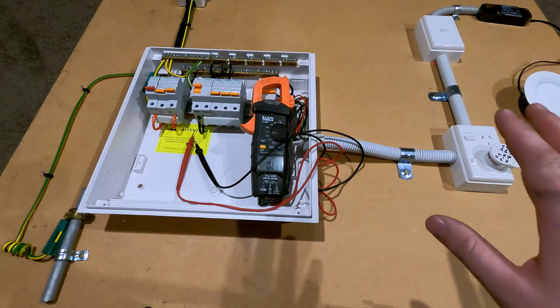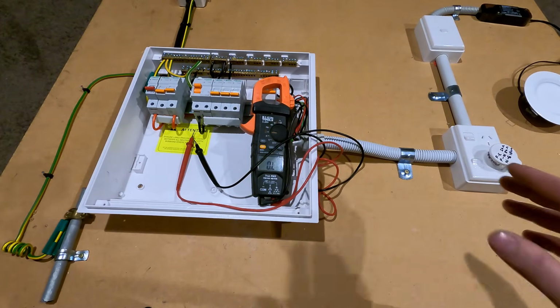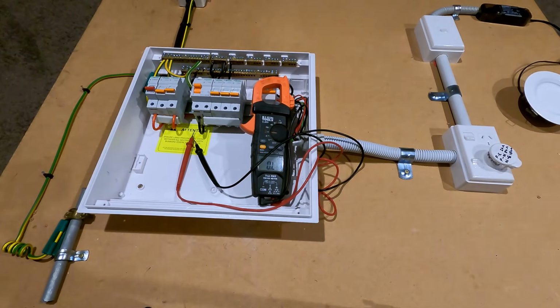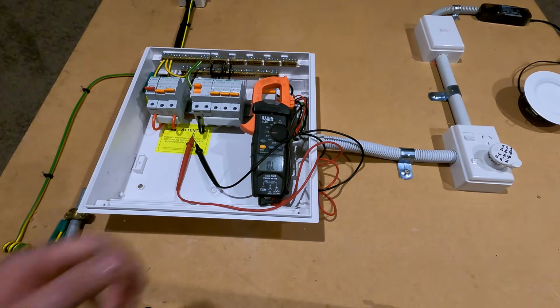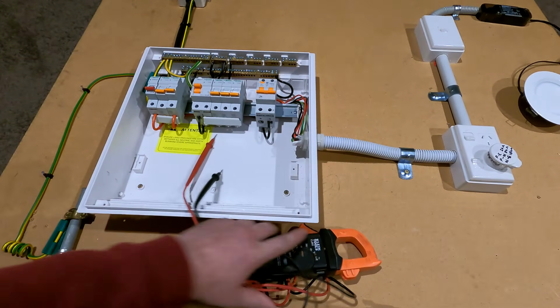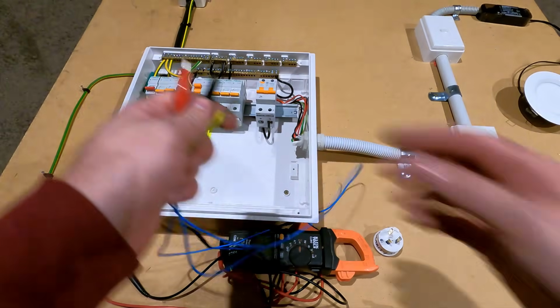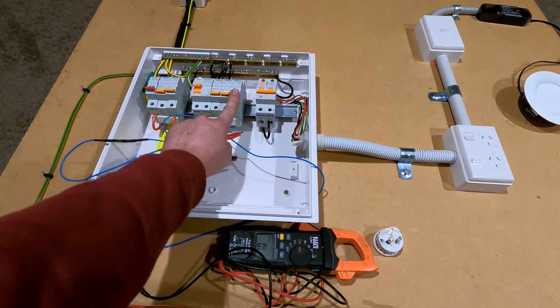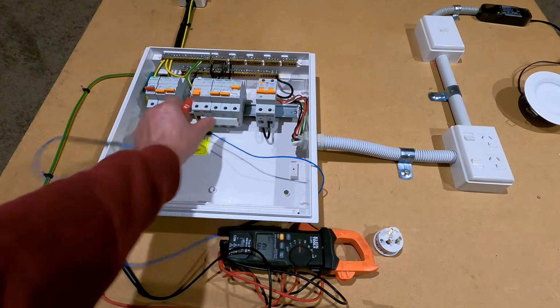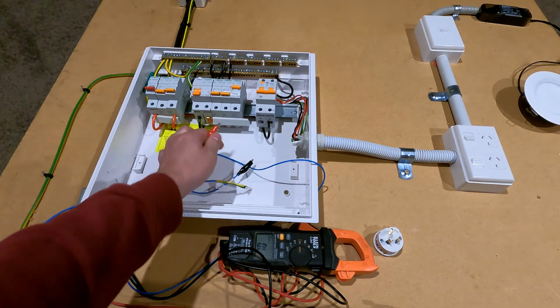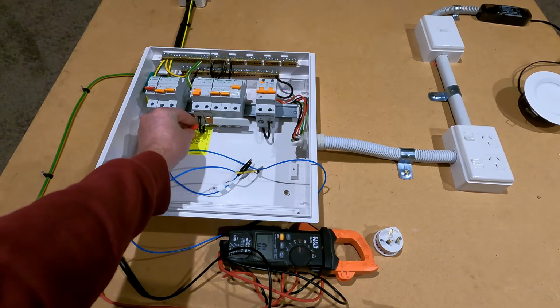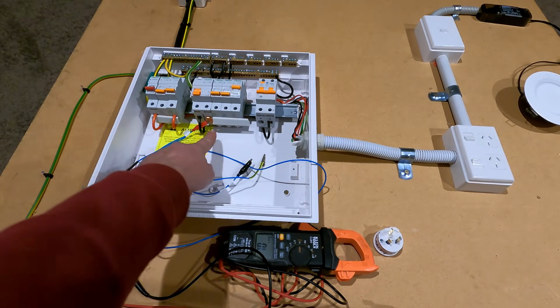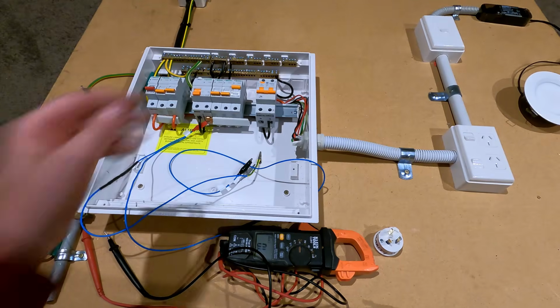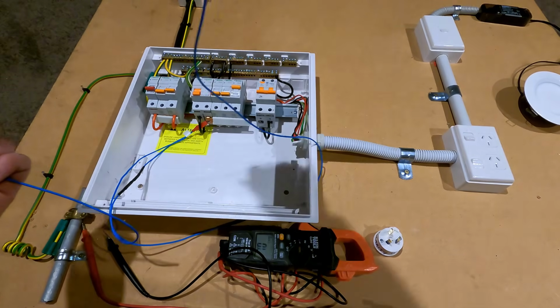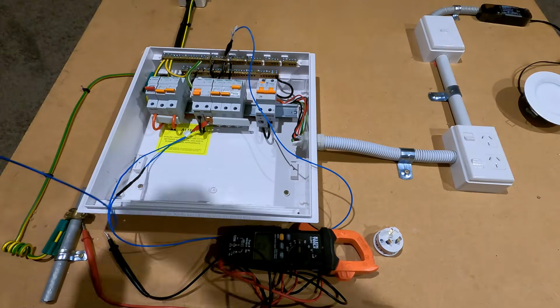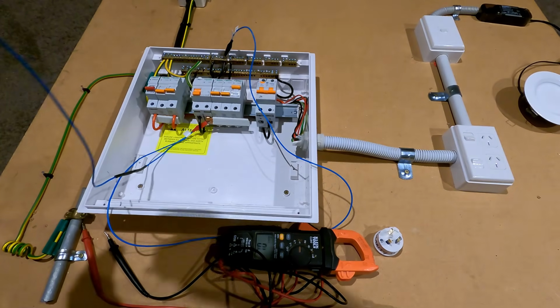So that's the first one shown, and it's pretty easy. It doesn't take too long to go around and verify all of the socket circuits. The next ones though are your lighting and appliances. So this next one, we've got our lighting circuit over here. So what I can do is turn it on, clip it onto the phase bar there, make sure it's not making contact with anything else. Obviously neutral onto the RCD neutral bar, and earth onto the earth bar.